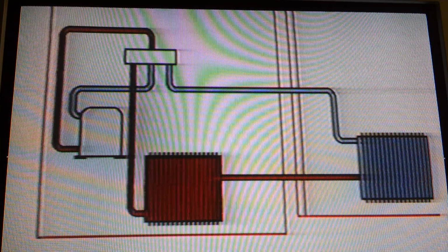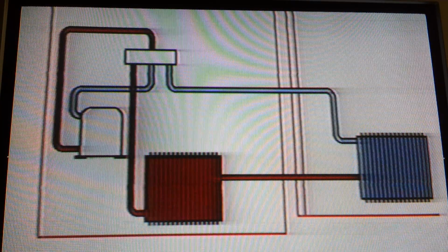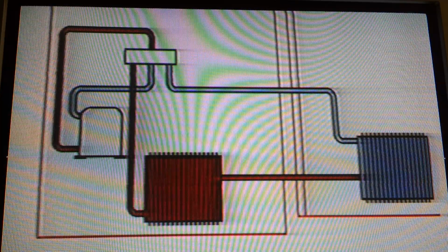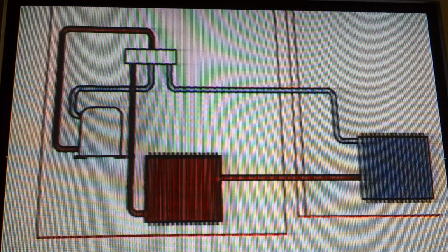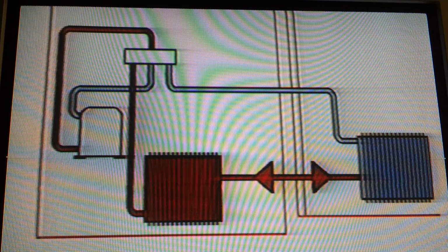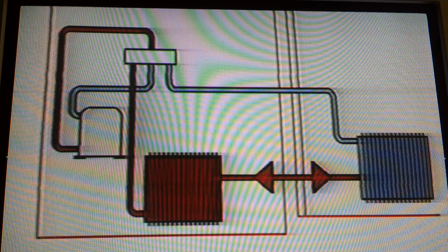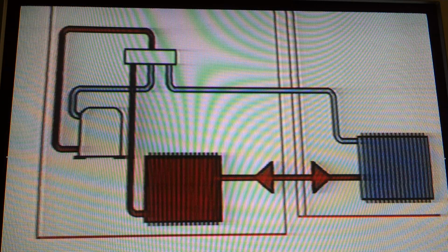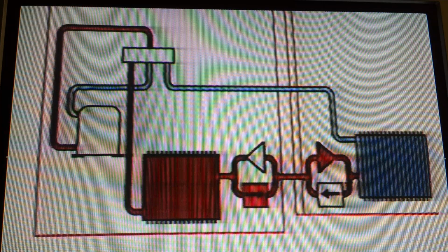Metering of refrigerant is a little more complicated than in a straight air conditioning circuit. One thing is certain about refrigerant metering in a heat pump. Each coil must have a metering device for use when that coil is operated as an evaporator. In many heat pump designs, this means two separate expansion valves. Only one of the valves is used at a time, however, so a check valve must be used to route the refrigerant around the other valve.